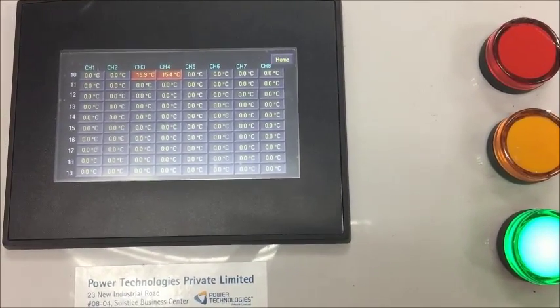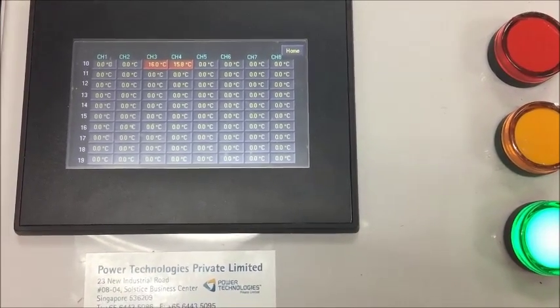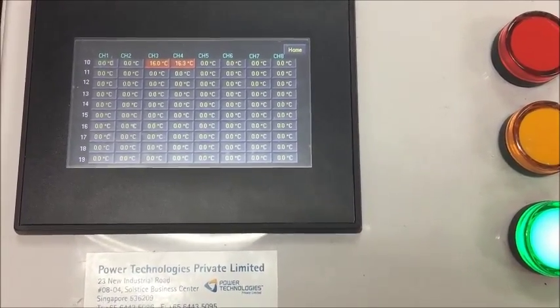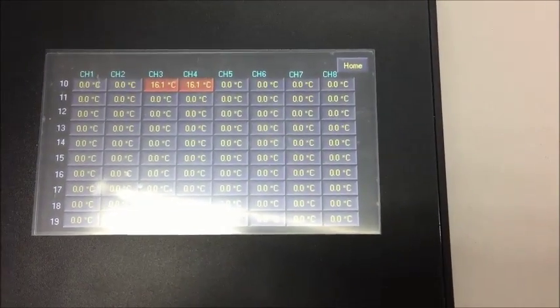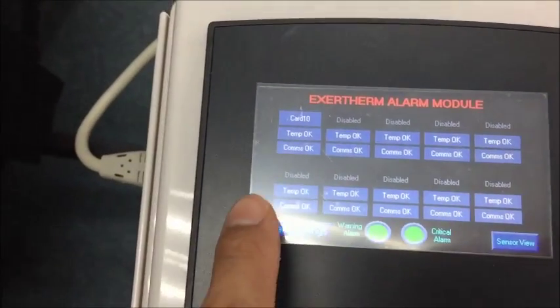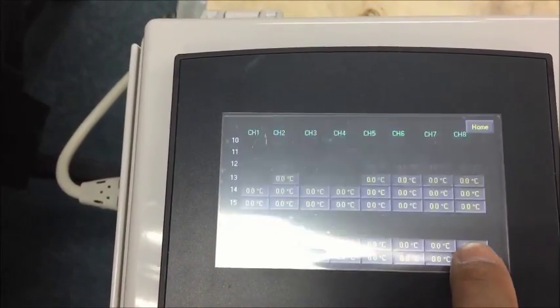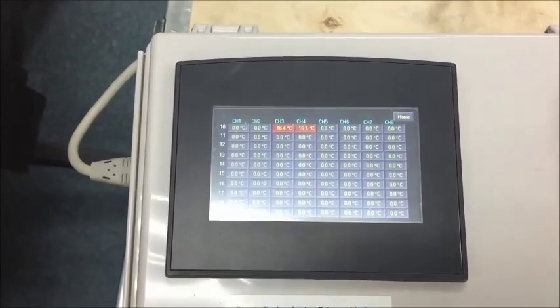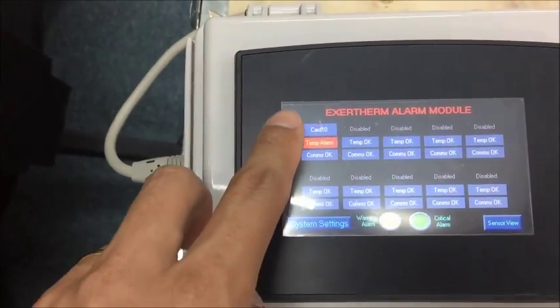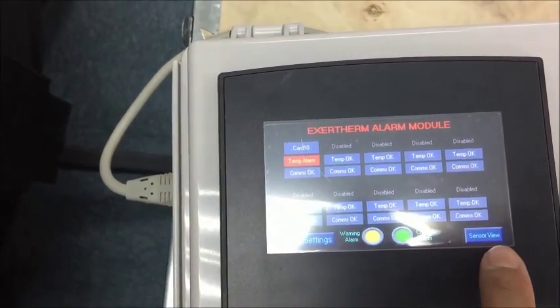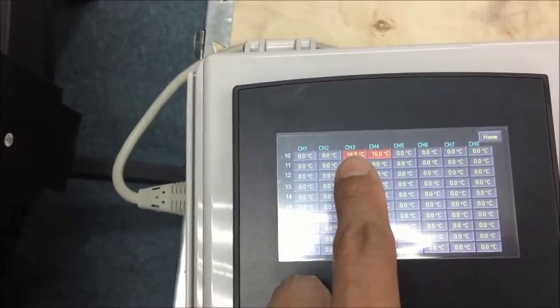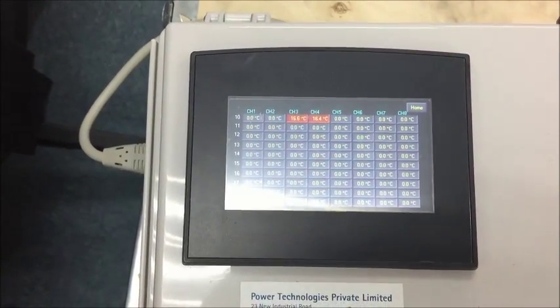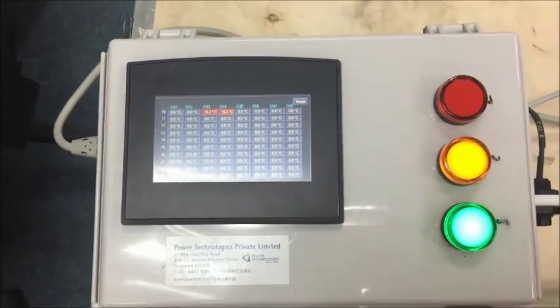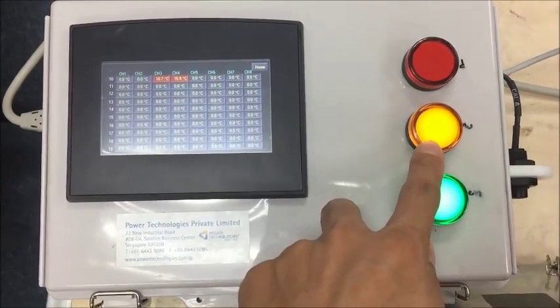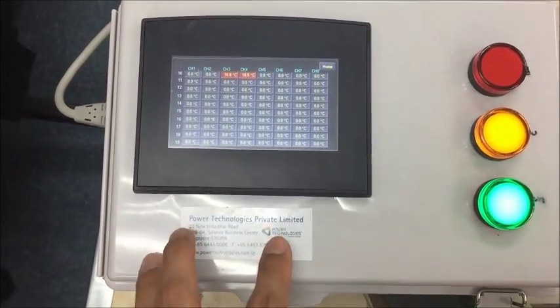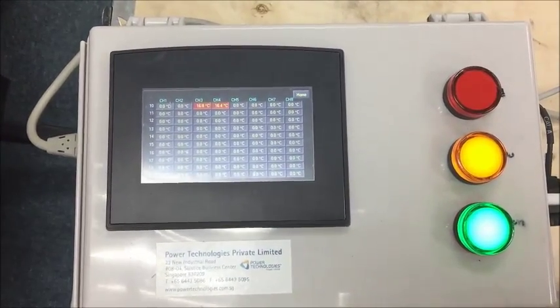So you hold, and it's quite constant and consistent now, so it has detected this as a loose connection hotspot. From the home screen you can see there's nothing here, still stable. When you see the alarm, you can see data card 1 temperature alarm, so you can go to sensor view, and then you know channel 3 and channel 4 have hotspots, and you go and rectify it. At the local panel you will have warning lights. If you have remotes, they get another light at your BMS system.